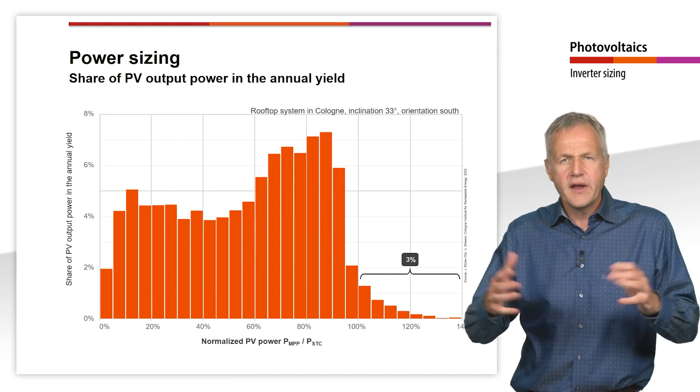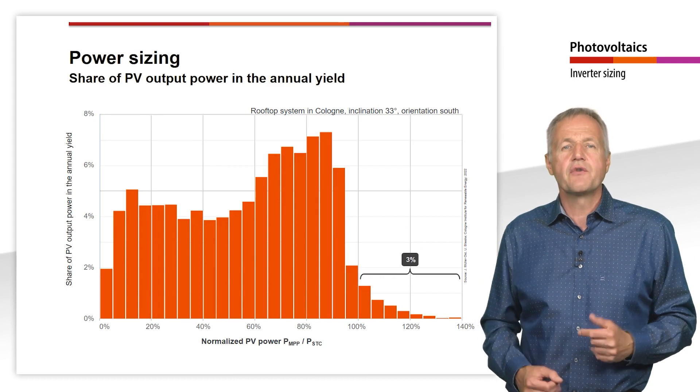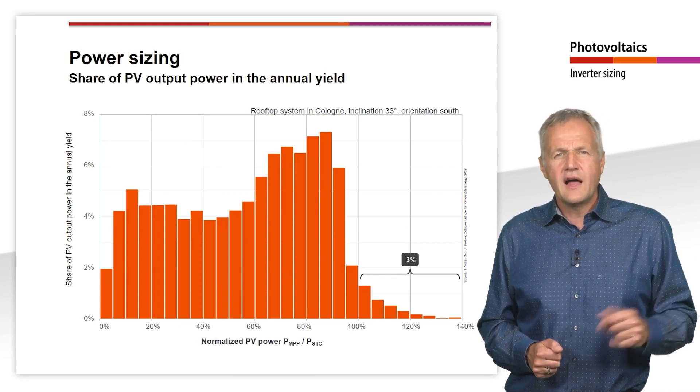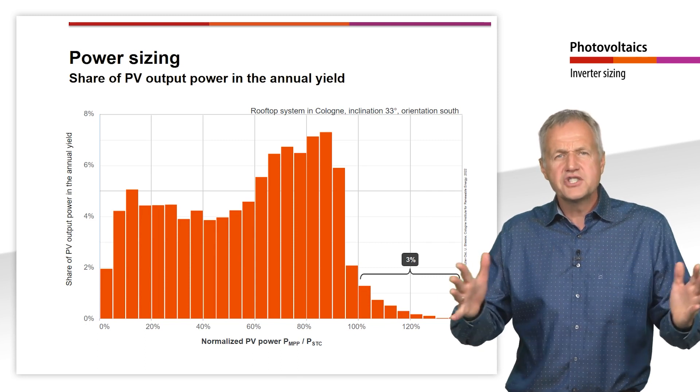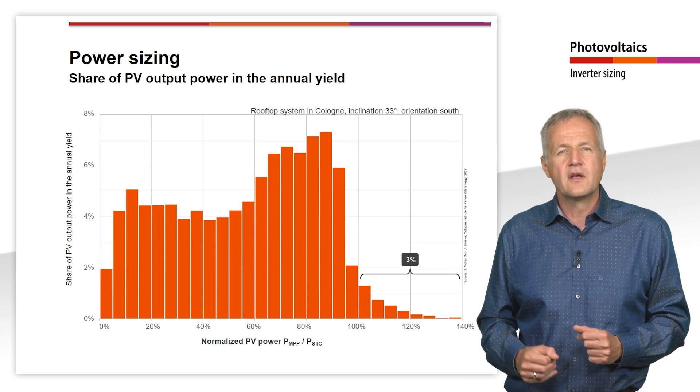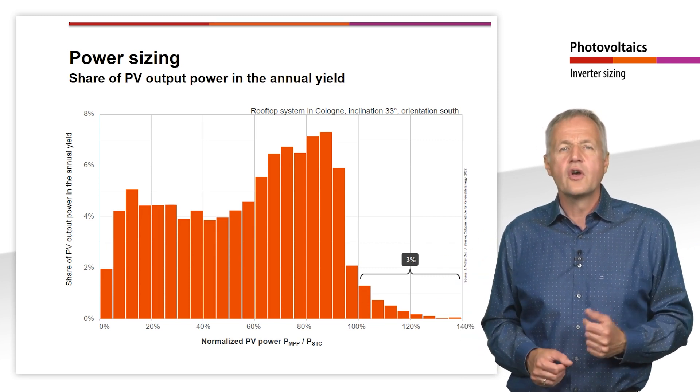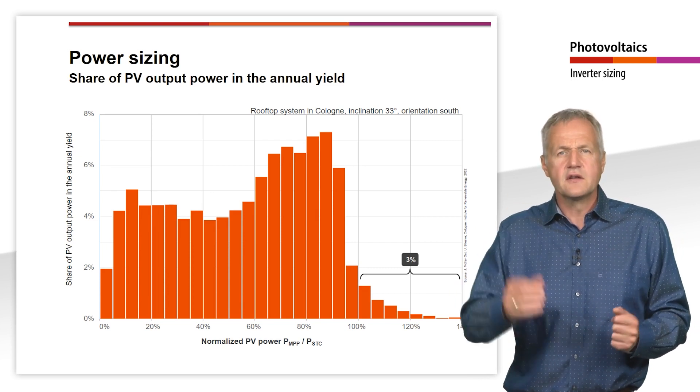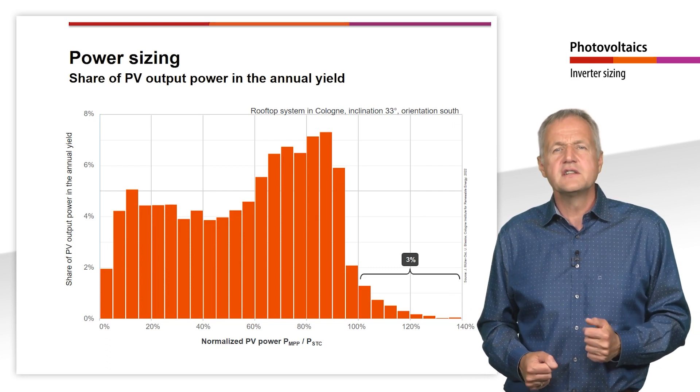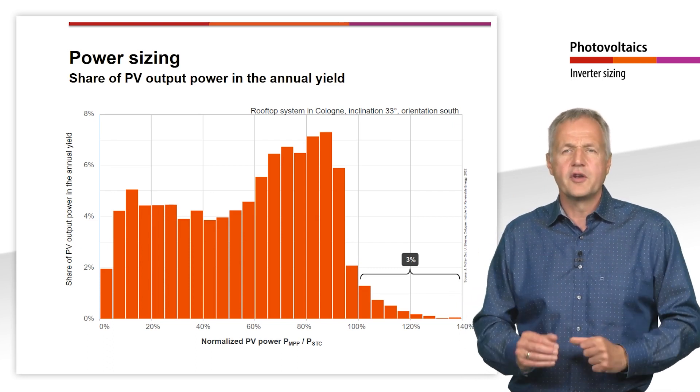Due to the correlation just explained, the nominal power is very rarely reached during normal operation of a PV module. The largest share of the annual energy yield is therefore generated at lower PV outputs. Let us again consider the example of a rooftop system in Cologne with an optimal tilt angle. Here about 97% of the annual energy yield is generated at system outputs below the nominal output.